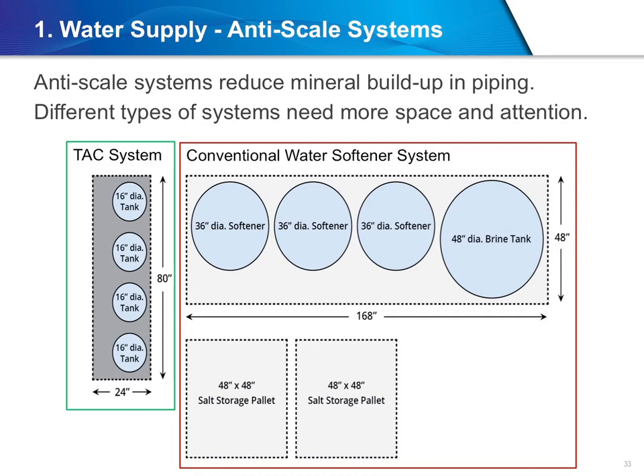Scale is related to potable, clean drinking water that has a high mineral content and is referred to as hard. Over time, the minerals can attach to the metallic surfaces of a water system and start to build up. The resulting scale often becomes encrusted on the internal moving parts of valves and components, affecting their intended purpose and potentially causing safety failures. In a boiler or hot water tank, heating elements can become coated with scale, reducing system efficiency and safety. In pipes and other components, scale can restrict water flow and create potential breeding grounds for bacteria.